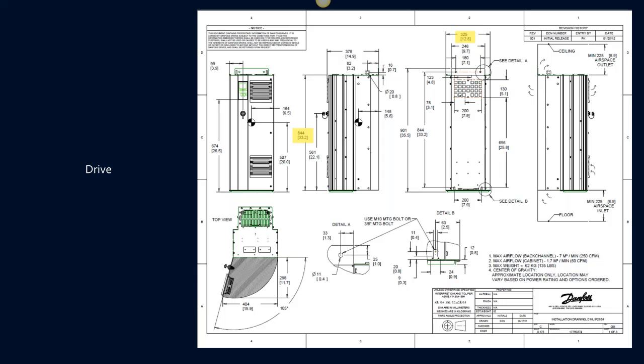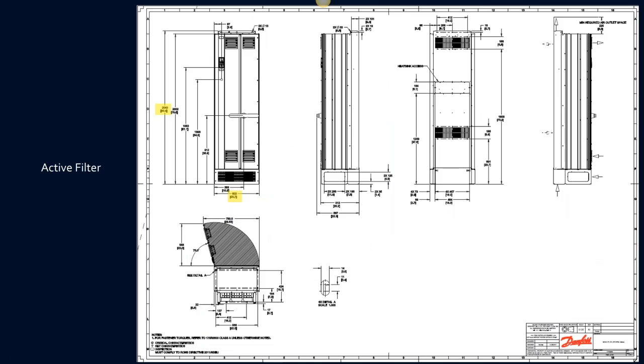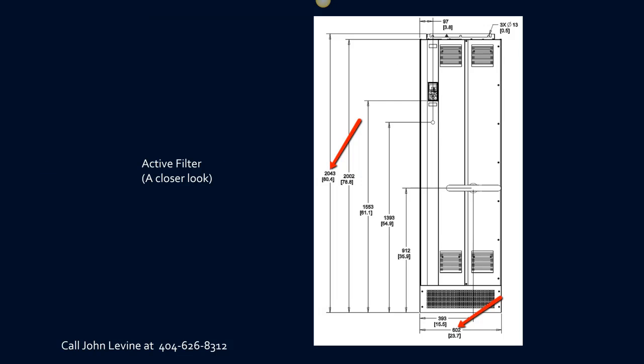This is the drive, and this setup is 12.8 inches wide for the drive. And we have an active filter here that is 23.7 inches wide. I got that highlighted here. You may not be able to see that, but here's a better view of the active filter. It's 23.7 inches wide and 80.4 inches tall. And this filter will usually handle the harmonic correction for 3, 4, 5, 6 drives in a lineup.